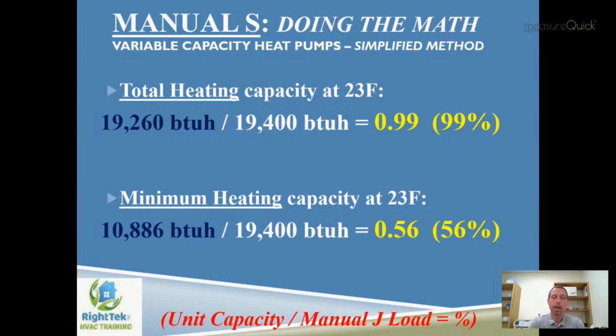They're finding a lot of failures in variable capacity, inverter-driven heat pump systems. They're finding a lot of premature compressor failures. And what they're finding is that folks are going out there and saying, oh, it's a variable capacity system. It's an inverter. If I need a 2-ton, why don't I just put in a 3-ton? Then I know I got plenty of capacity, especially for heat. And in cooling, it will just ramp down and it'll run at a lower capacity.